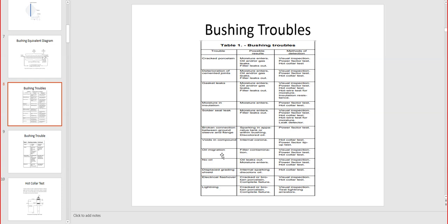So it is a problem if the bushing is not cooled properly. Normally the bushing on the top of the transformer has its own chamber. So the transformer overall has 3 chambers: the main tank, the bushing on the top, and then the actual tap changer. Sometimes the top of the transformer for the bushing has some nitrogen that is used for insulation and cooling. So the oil needs to be present in the bushing all along, so we cannot fail that. If the oil leaks out, moisture enters, so we cannot have that.